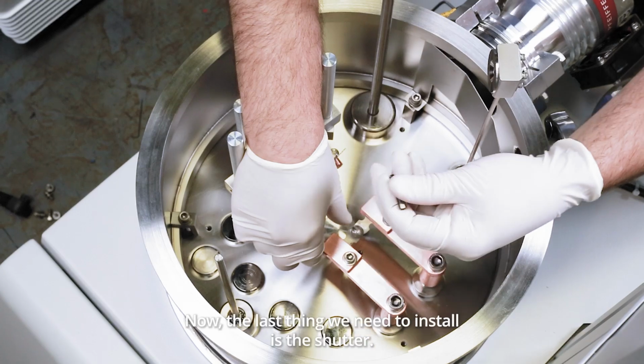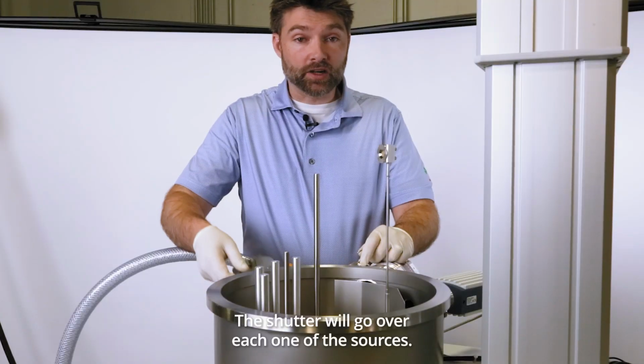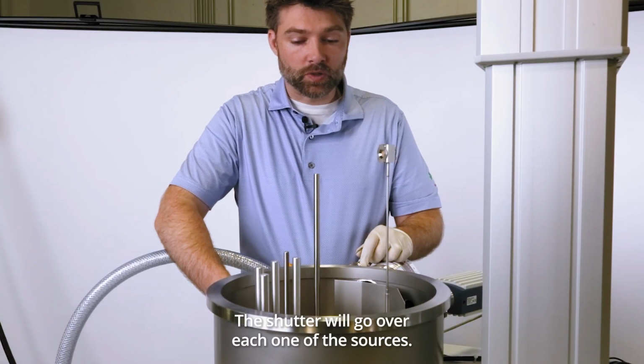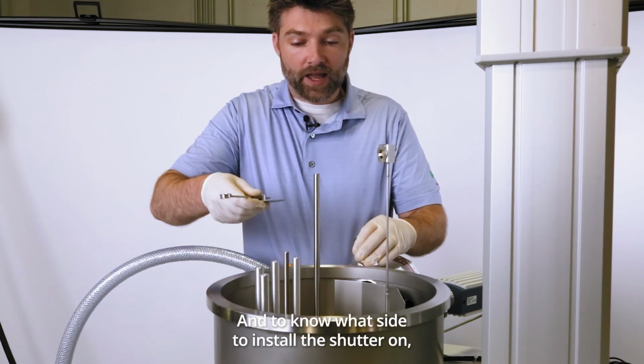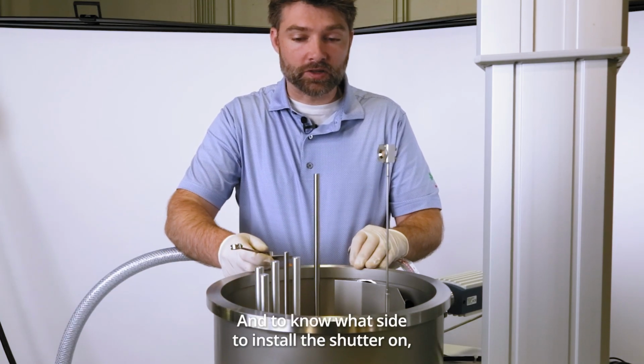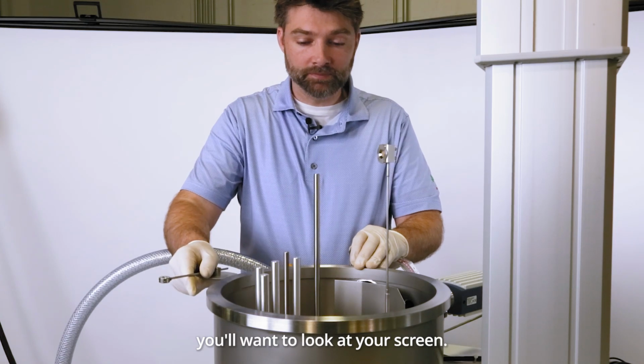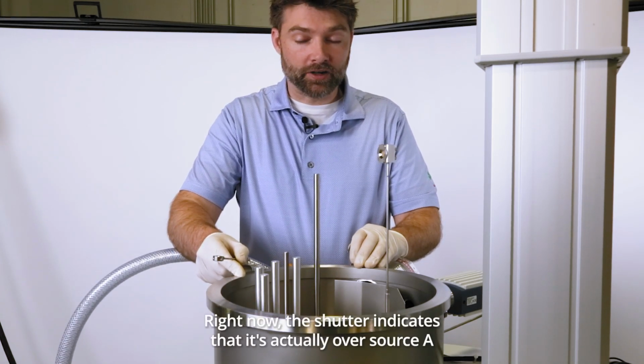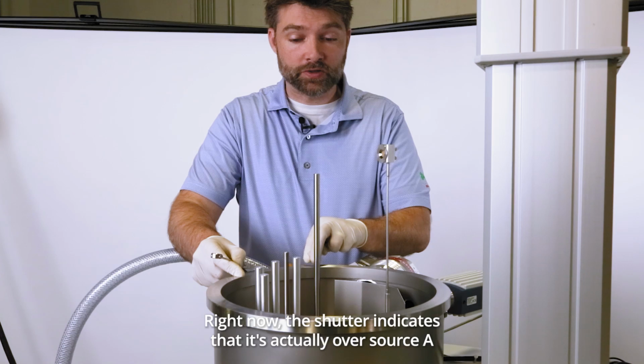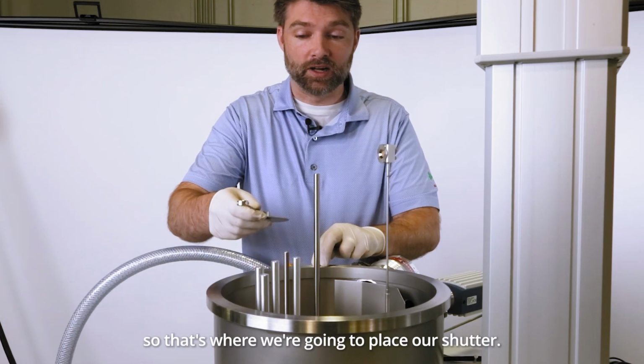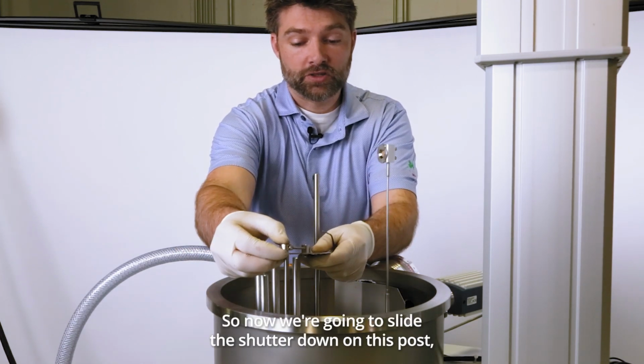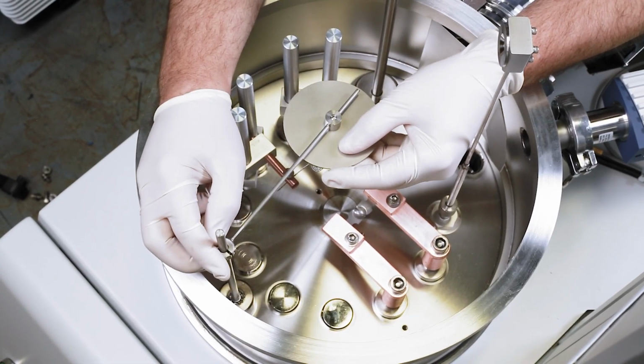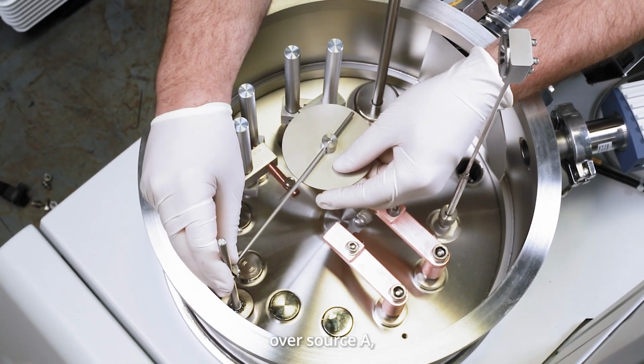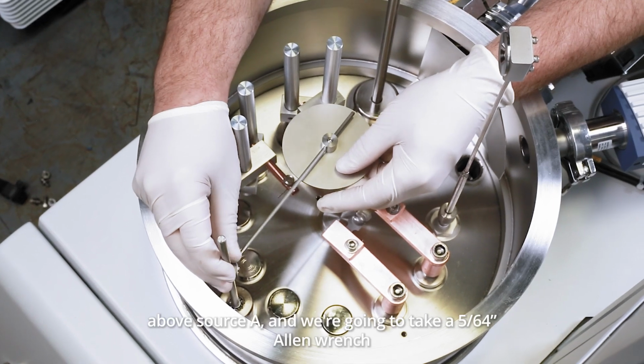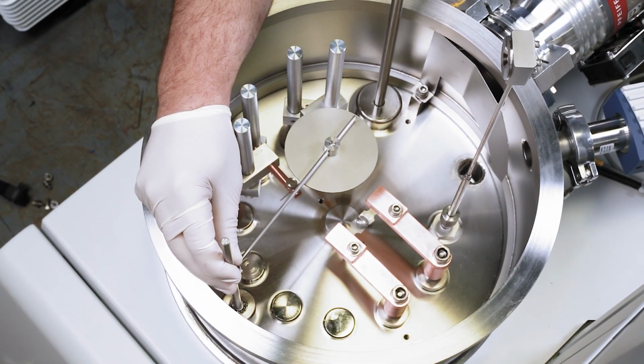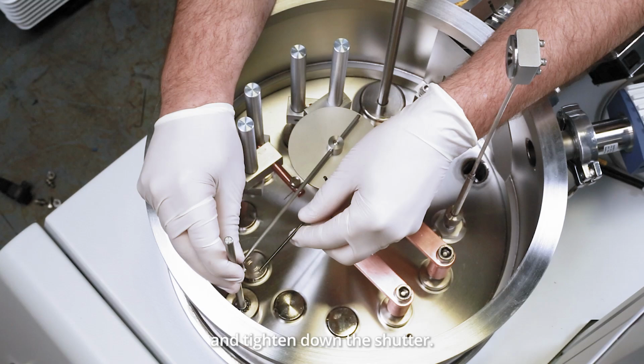Now the last thing we need to install is the shutter. The shutter will go over each one of the sources, and to know what side to install the shutter on, you'll want to look at your screen. Right now, the shutter indicates that it's actually over source A, so that's where we're going to place our shutter. So now we're going to slide the shutter down on this post, over source A, and we're going to take a 5/64 Allen wrench and tighten down the shutter.